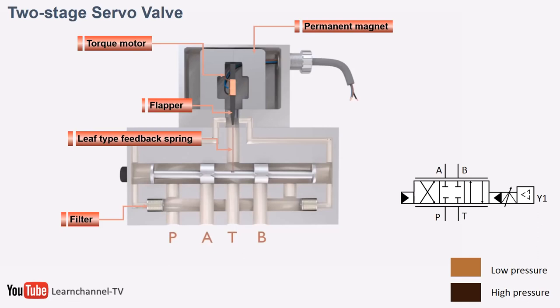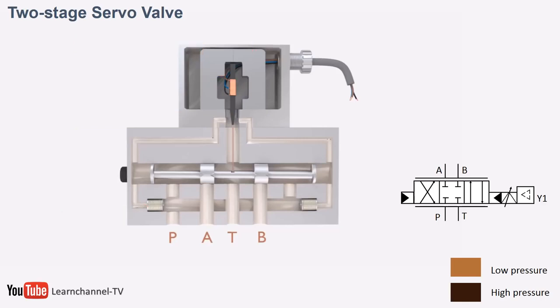The main difference between proportional and servo valves is that servo valves have a feedback of the spool which can be used as an internal signal for the controller to adjust the valve itself.